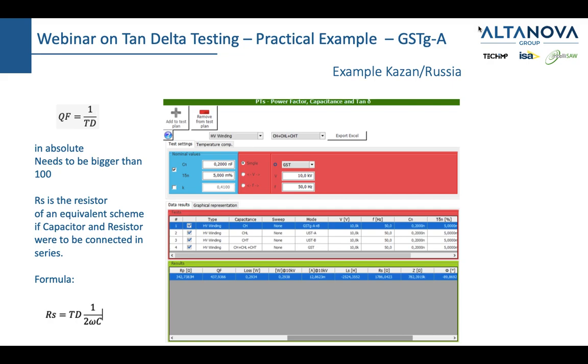For tan delta in the C2 test, the values should be less than 1%. Well, it depends how your bushing is made. Is it resin impregnated paper or something else? I think the best thing would be to ask your producer, because usually for bushings even lower values of tan delta are advised, even though I've seen some tables where bushings for certain modes of production can be up to 2 or 3%. So that depends on how the bushing was made.